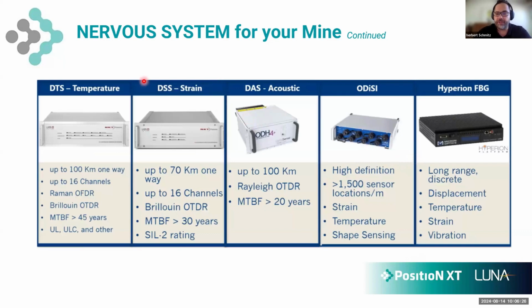We, however, have various different technologies using fiber optic sensing. We have temperature sensing systems that can sense up to 100 kilometers per channel and up to 16 channels. We have strain systems where we can measure strain or stress along the fiber optic cable. We have acoustic sensing systems where we can measure vibration. We can measure eddies and airflow, any turbulent flow, and very high sensitivity, short range, but very high resolution sensing systems as well.